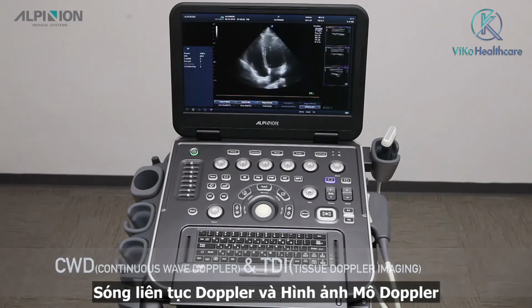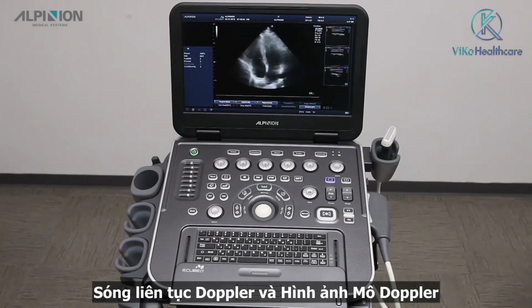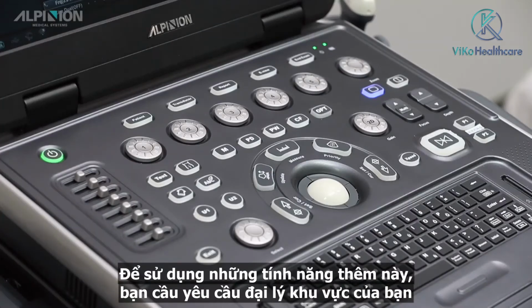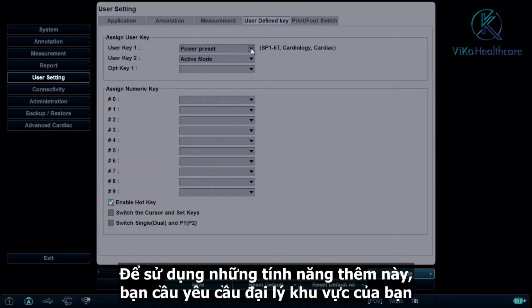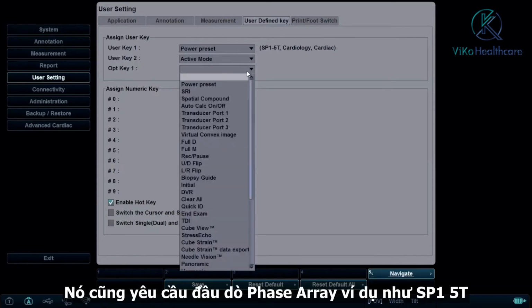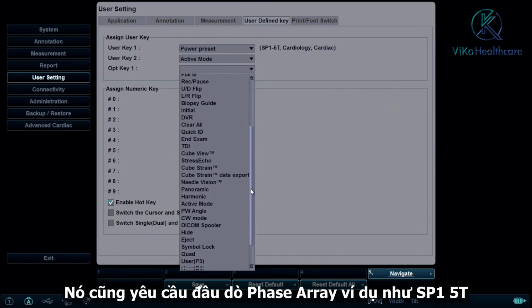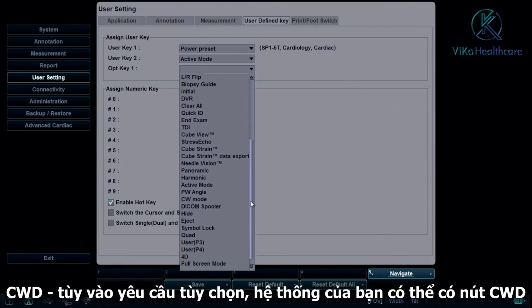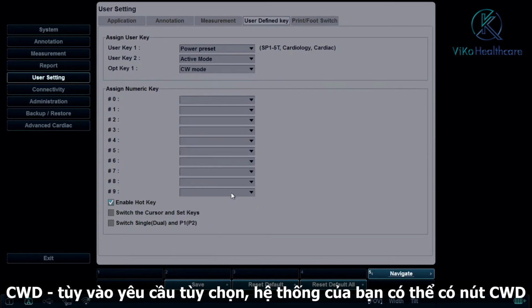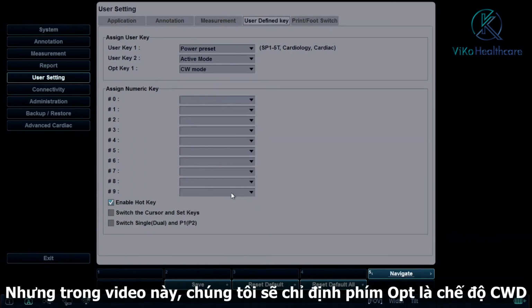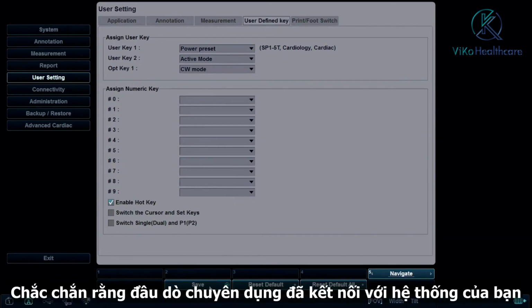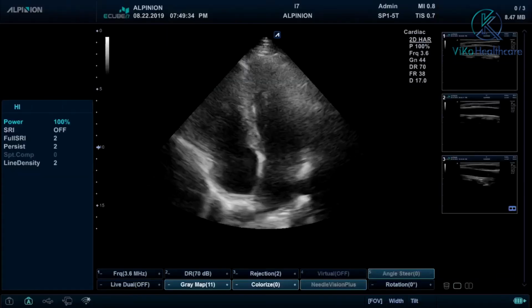Continuous wave Doppler, tissue Doppler imaging. For using those features, you need an additional request to your local agent. It also requires the phased array transducers such as SP1 5T. CWD. Depending on the option, your system may have CW key. But in this video, we will assign Opt key to CWD mode. Make sure that the dedicated transducer is connected to your system.